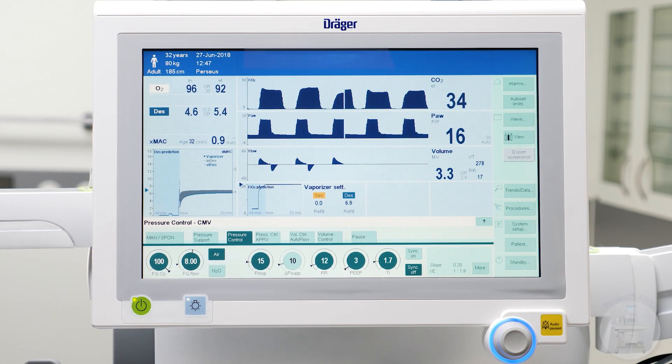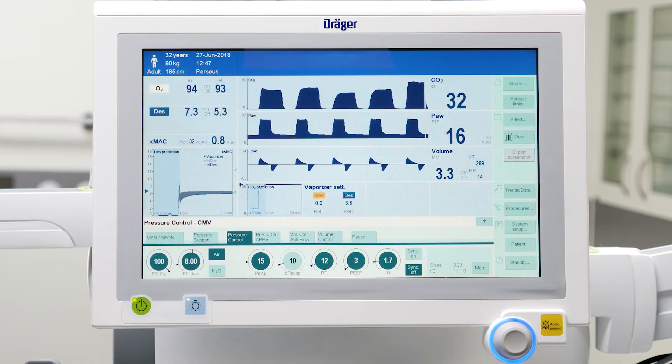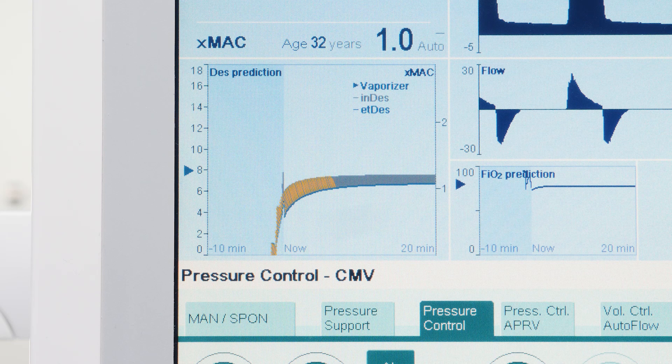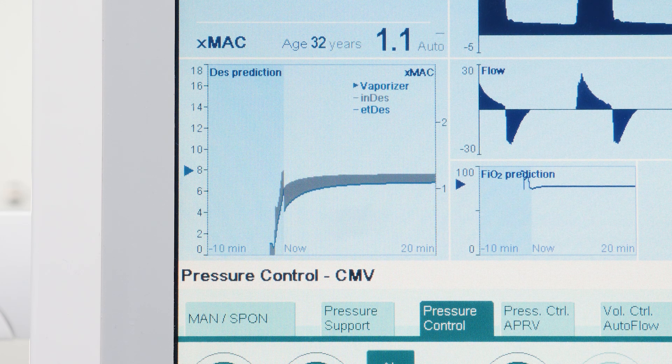Draeger Perseus A500 can offer the intelligent predictive functions VaporView and O2 prediction when used in conjunction with Vapor 3000 and D-Vapor 3000. The system visualises both the inspiratory and the expiratory volatile agent concentration and the inspiratory oxygen concentration prediction over the next 20 minutes, along with a trend of the past 10 minutes. These features offer higher levels of safety and transparency and make the recovery phase easier to manage.